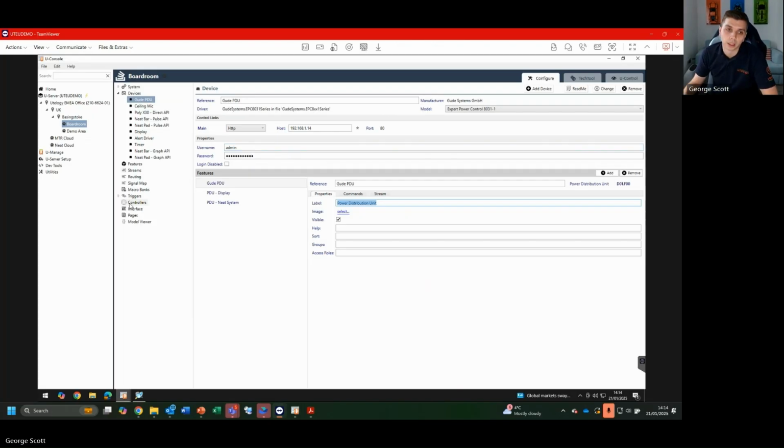Okay. The only other thing we're going to set up as part of the demo is what we would term a self-healing scenario. A really important thing we implement when we build out these systems is determining the use cases for when a self-healing scenario takes place. That's where something is determined to be an issue in a space, not in an optimal or compliant state, so it's not working the way it should. We can detect that and put it right without a user or technician having to step in and make that change.